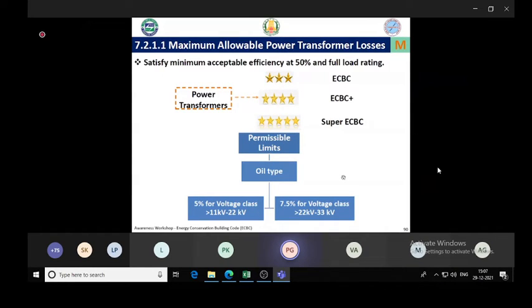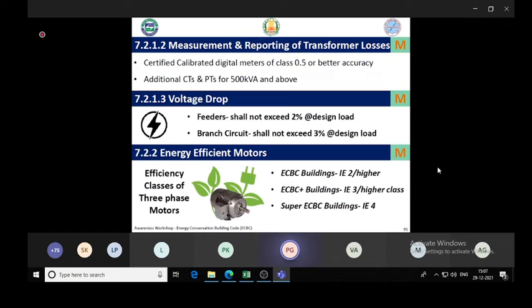Okay. And there are voltage drop requirements. So when we design the electrical system, in the feeders the voltage drop should not exceed 2%, and in branch circuits it should not exceed 3%.